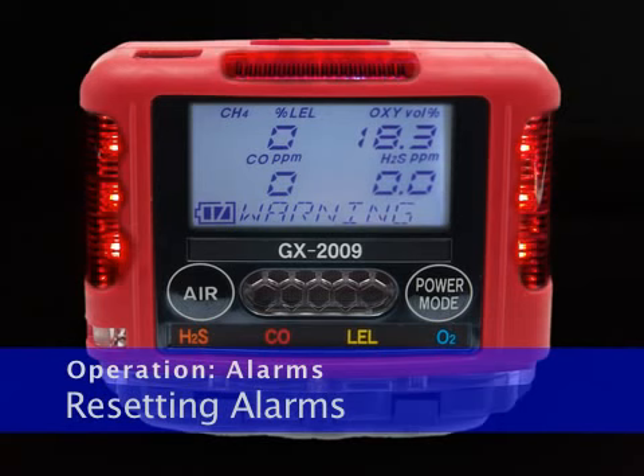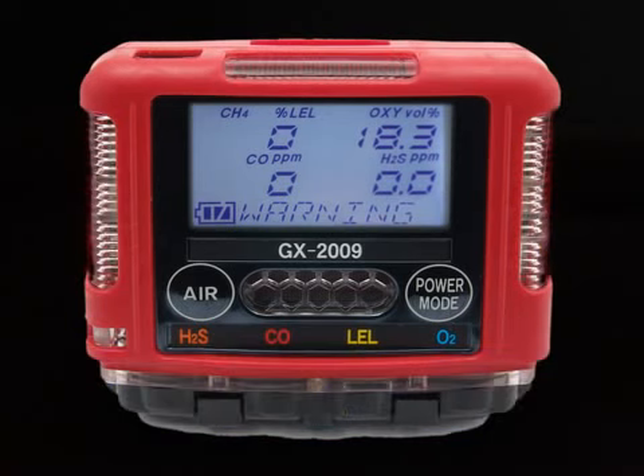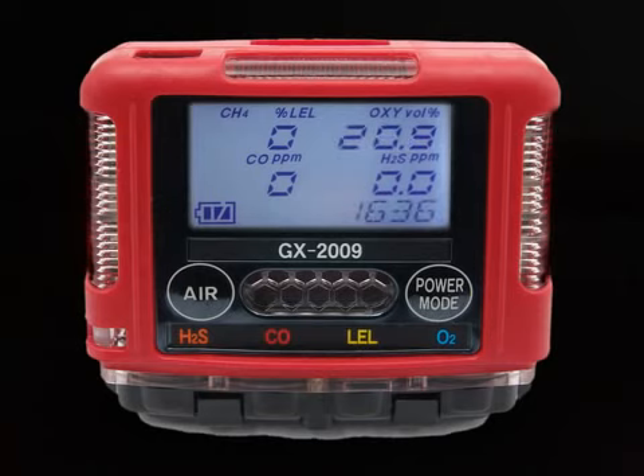To reset latch-in alarms, press and release the power mode button after the gas reading falls below the alarm set point, or above for oxygen warning. If the alarms are self-resetting, then an alarm condition will automatically reset when the gas reading that caused the alarm decreases below the alarm set point, or increases above for oxygen. If a STEL or TWA alarm has been activated, it cannot be reset. You must turn off the unit to clear the alarm.